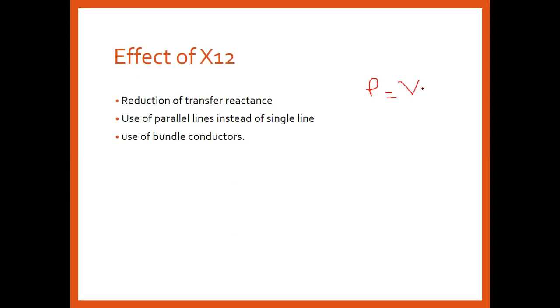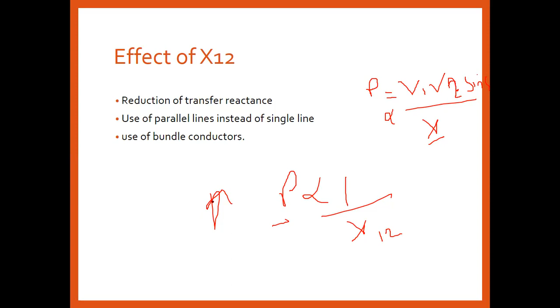So X has an inversely proportional relation, and P is inversely proportional to the reactance between the two buses, X12. So the more the reduction, the more the power improves. Power improves, and stability improves. Parallel lines are generally used instead of single lines, and bundle conductors are used to reduce the reactance of the transmission line, so as to improve the power and lower down the losses.